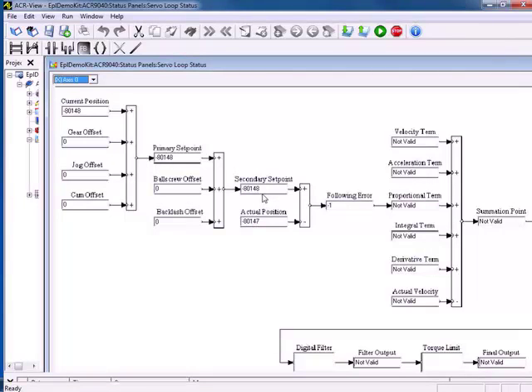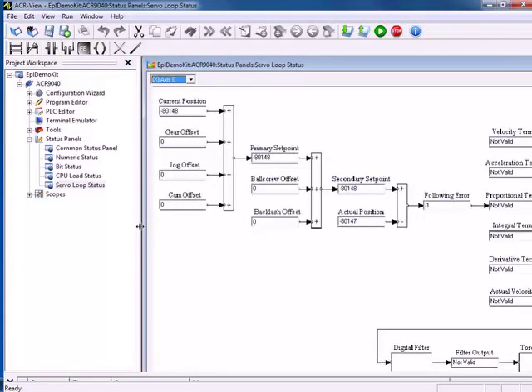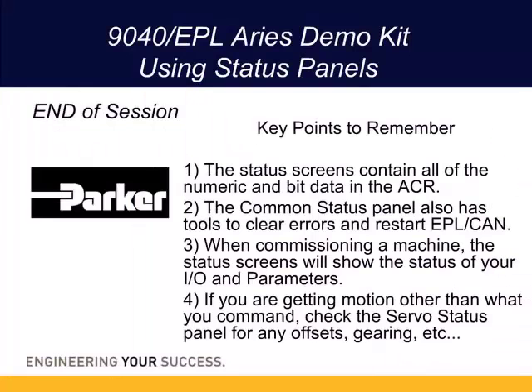That concludes our session for the status panels. This has been the 9040 EPL ARIES Using Status Panels. Key points to remember are that the status screens contain all of the numeric and bit status in the ACR. The common status panel has tools to clear errors and restart the EPL and CAN open networks. When commissioning a machine, the status screens show you the status of your I/O and parameters. If you're getting motion other than what you command, check the servo status panel for any offsets, gearing, etc. Thank you for your attention and I hope this has been of use to you.